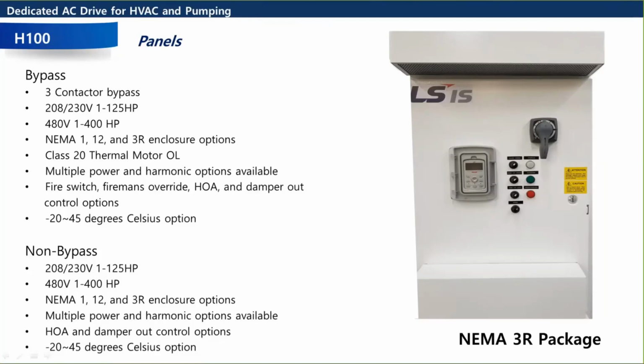That's a good question that I failed to mention. Can we have single phase input with 3-phase output? Yes, we can have that for all of our drives, and we've actually been UL tested and UL listed to run single phase in, 3-phase output, all the way up to 400 horsepower.